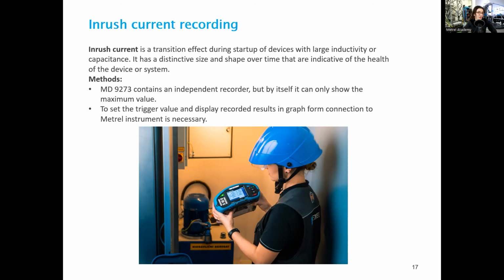So the MD9273 contains a recorder for inrush current. However, to use the full potential of this recorder, it is necessary to use the connection to one of the supported Metrel testers. This way, it is possible to use the current or voltage value trigger. We can set it up as any parameter in the instrument, and we can show the recorded data in graph form. Now, this graph, again, is very typical for each type of machine, and we can use it to diagnose problems with it.